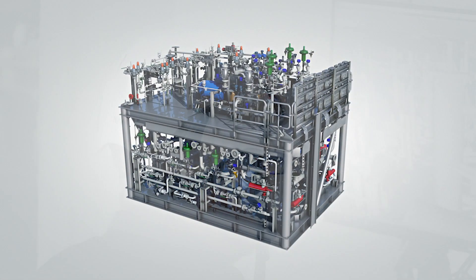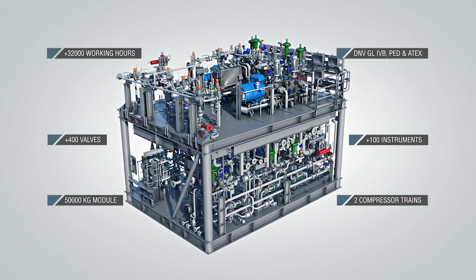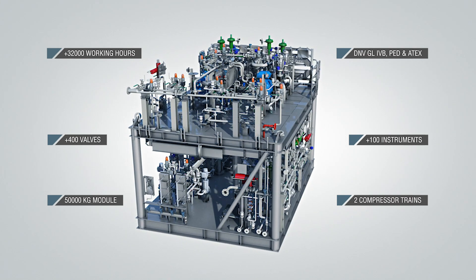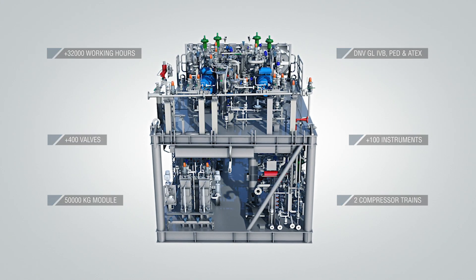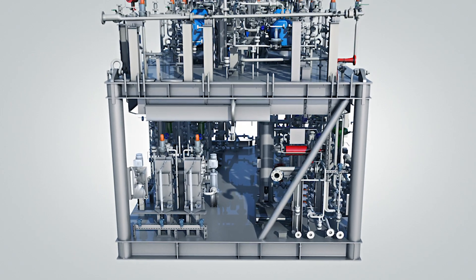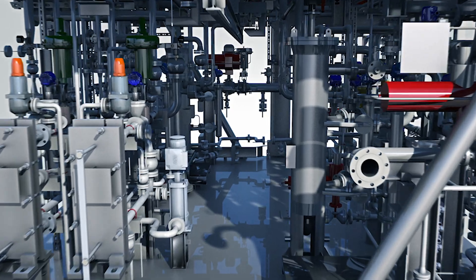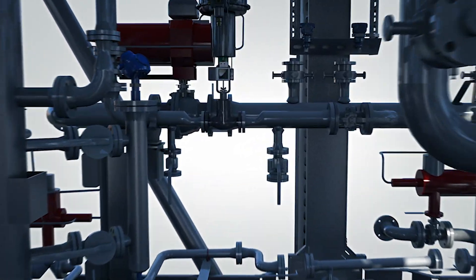This process module has a footprint of 5x7 meters and consists of two levels. It has two compressor trains working as duty standby, powered by electrical motors. It also has auxiliary systems for cooling medium, lubrication and seal oil. All in all, more than 400 valves and 100 instruments will be installed inside this module.